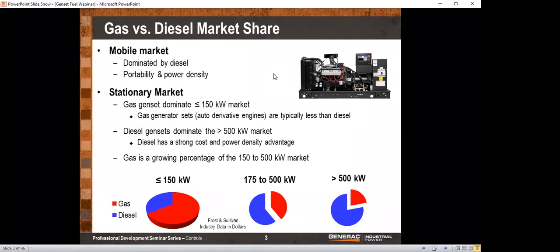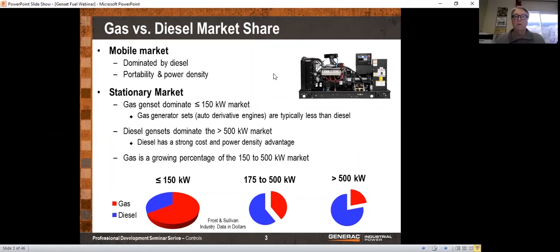In the stationary market, that's not the case. So let's take a look at the pie charts on the bottom. A 150 kilowatt diesel generator and a 150 kilowatt natural gas generator are basically the same price. As you get lower, the natural gas generator becomes less expensive. So just looking at an equipment procurement situation, you are going to be better off buying a natural gas generator below 150 kilowatts when it comes to capital cost.